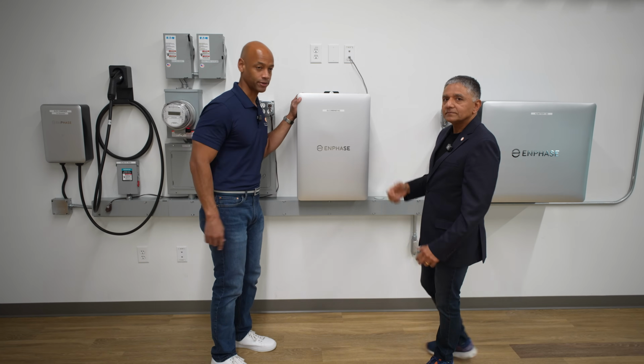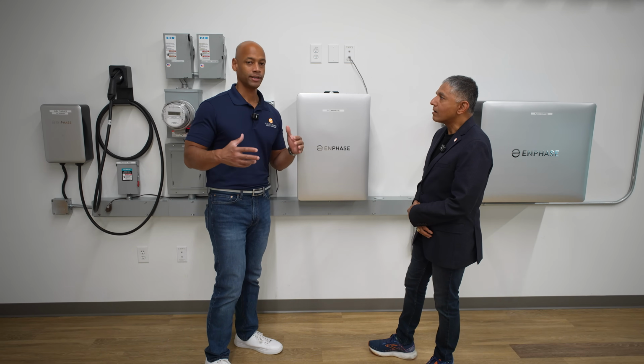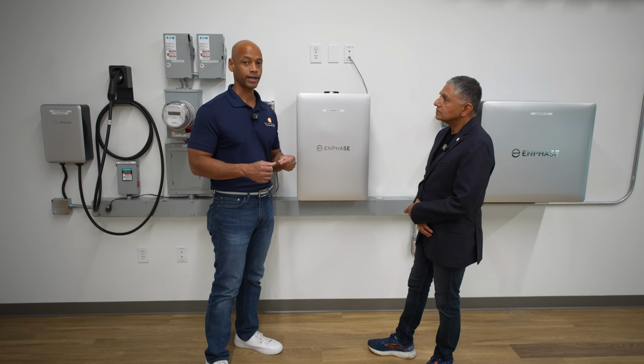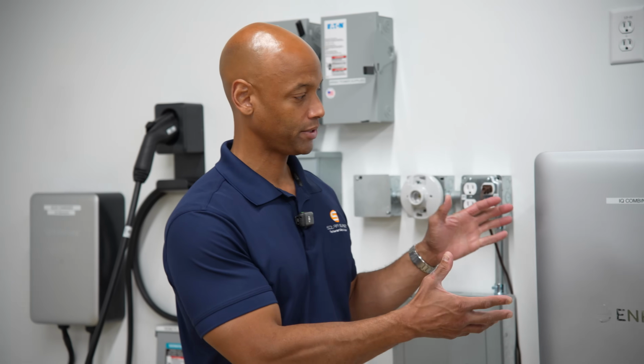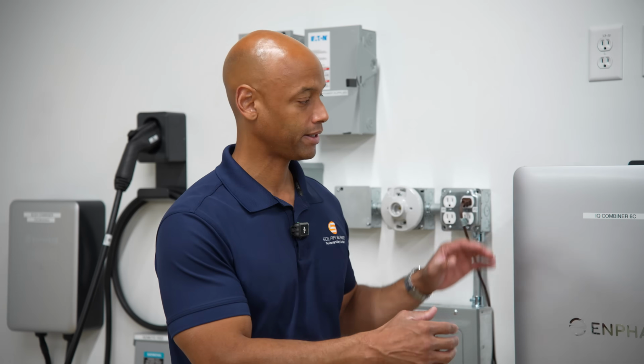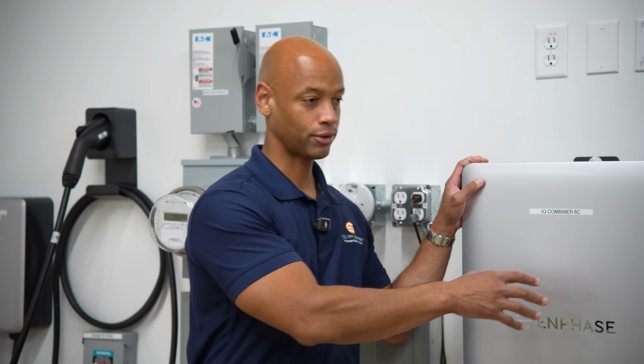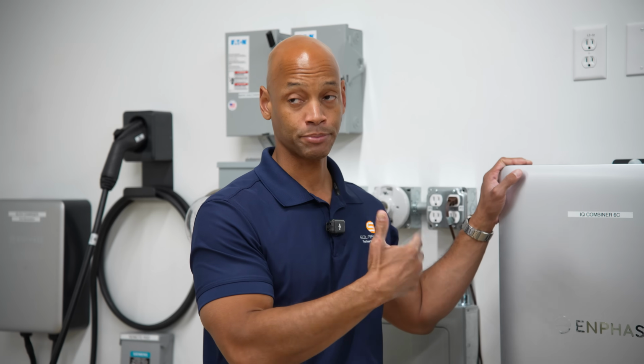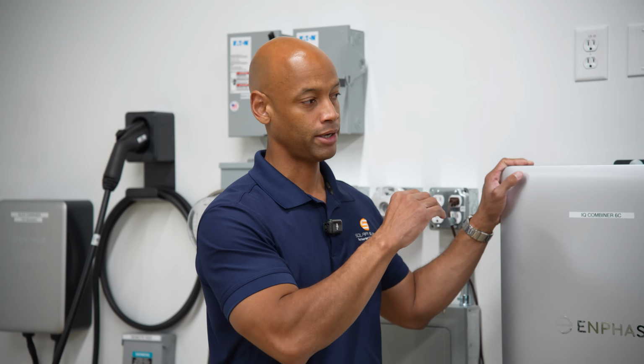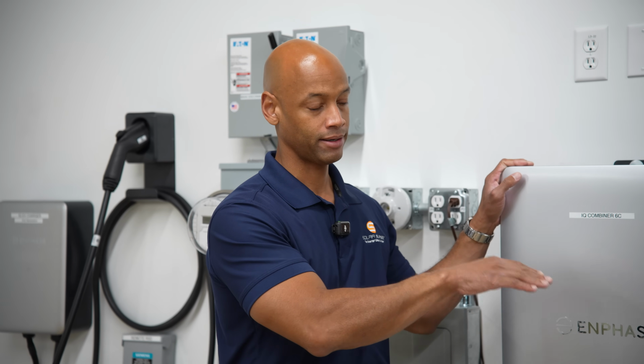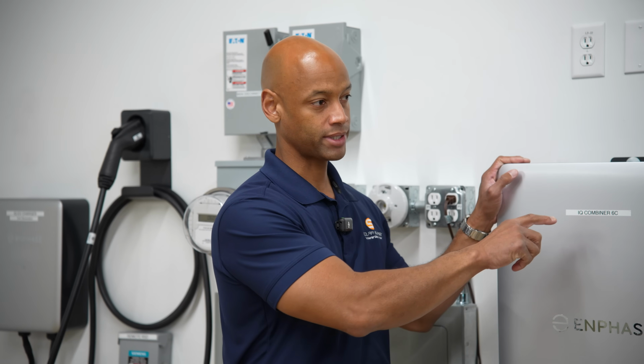Okay, so quick learning opportunity for you guys here. What we're talking about here is, let's say you have an electrical panel that's rated for 100 amps. Well, in theory, if you have a system here that could produce, let's say, 100 amps just from solar and battery alone, and you had a connection to the grid that could provide 100 amps also, then potentially you could have 200 amps of current feeding into your electrical panel, which could overheat and cause a fire. So what we're talking about here is basically this combiner is going to make sure that regardless of how much power is potentially available from all those different sources, no more than 100 amps is going into that load center, if that's what it was set for.